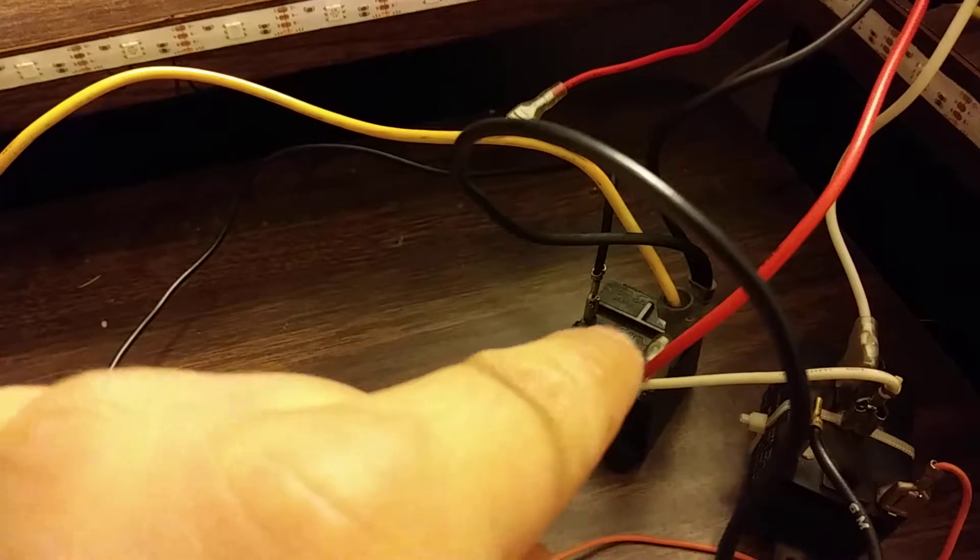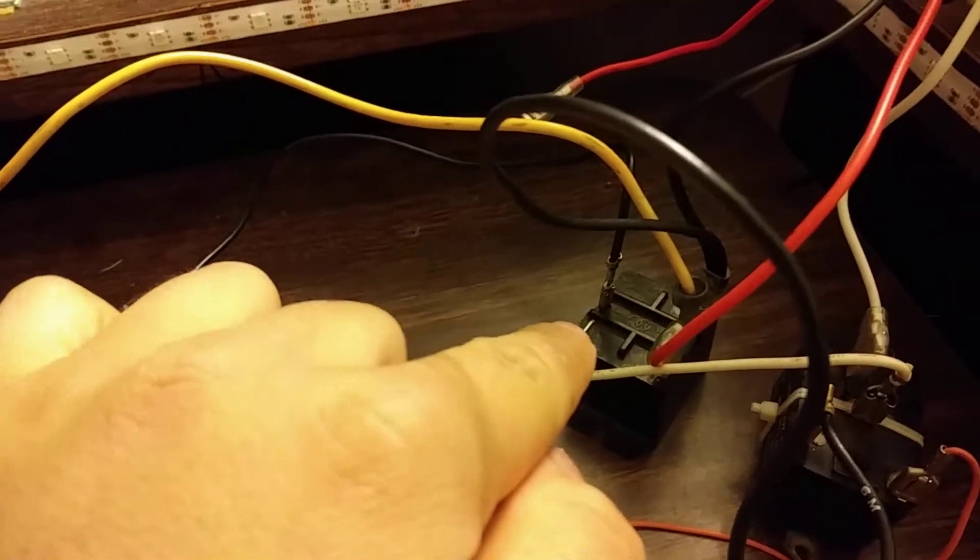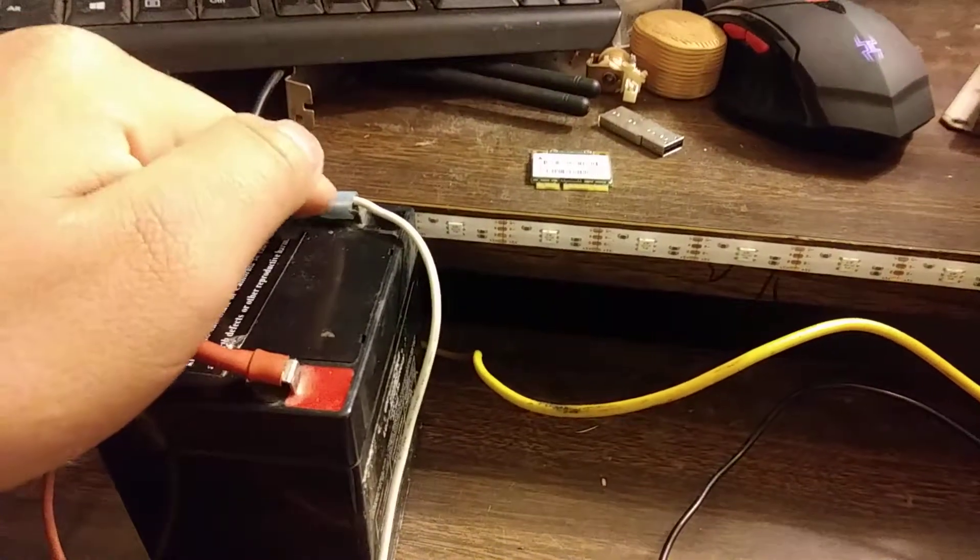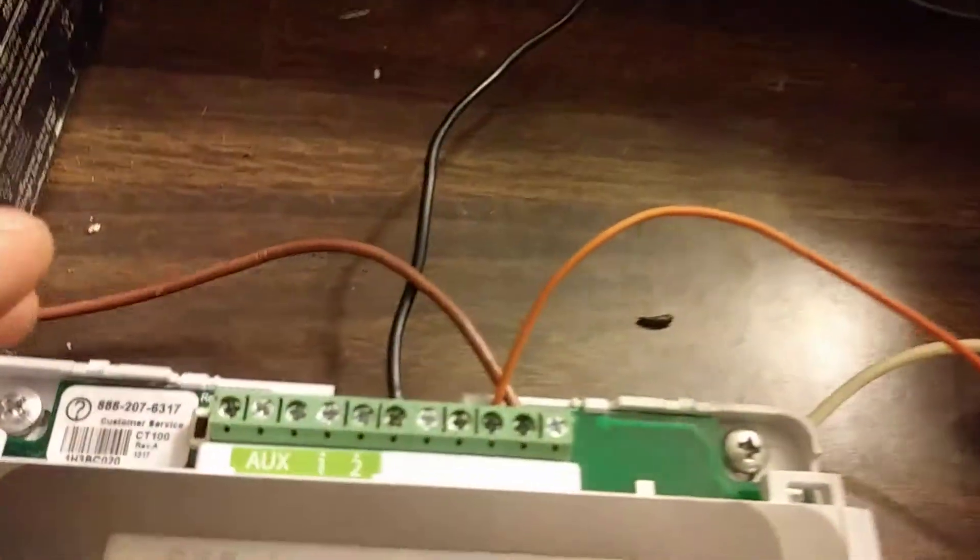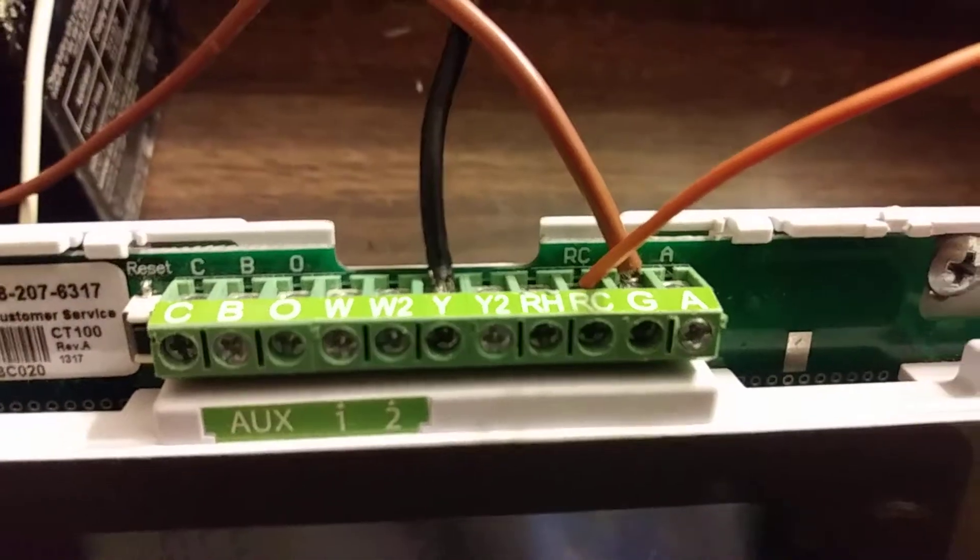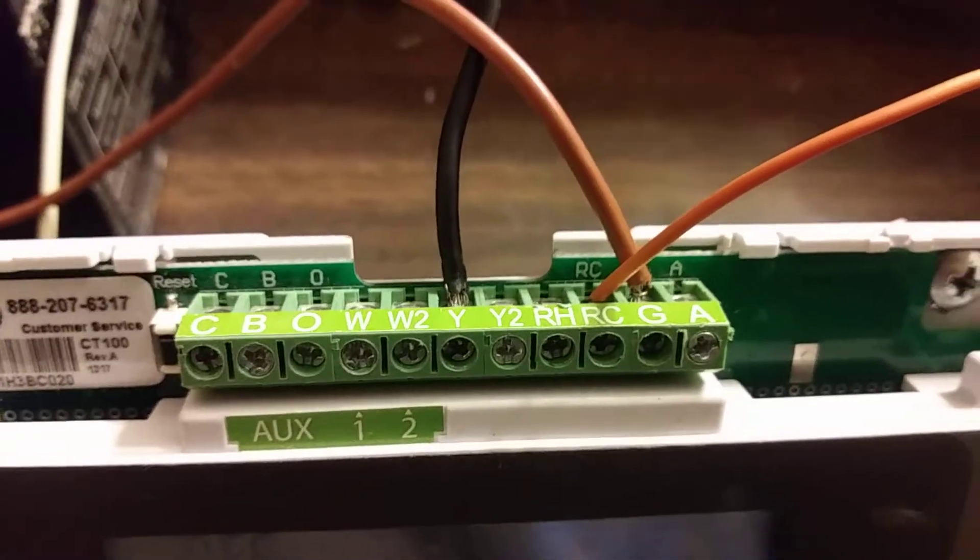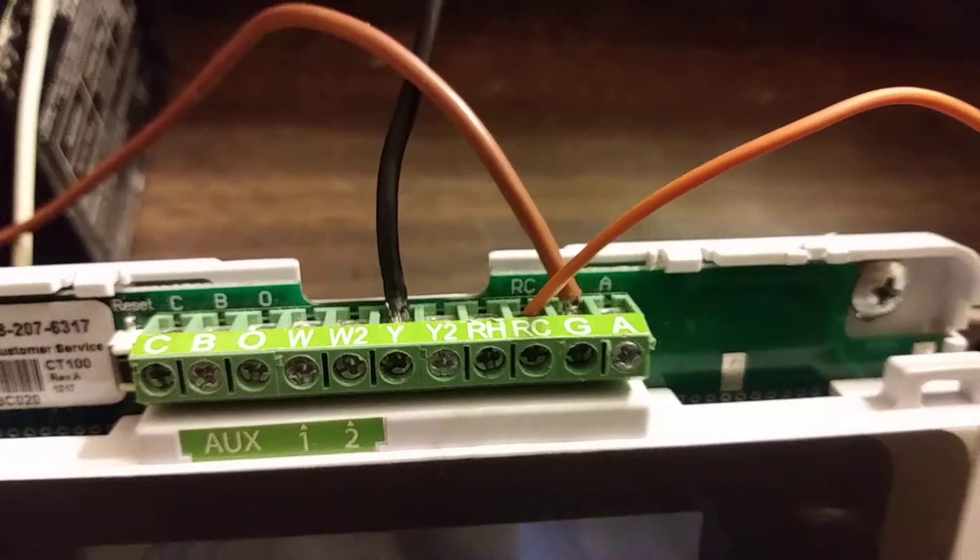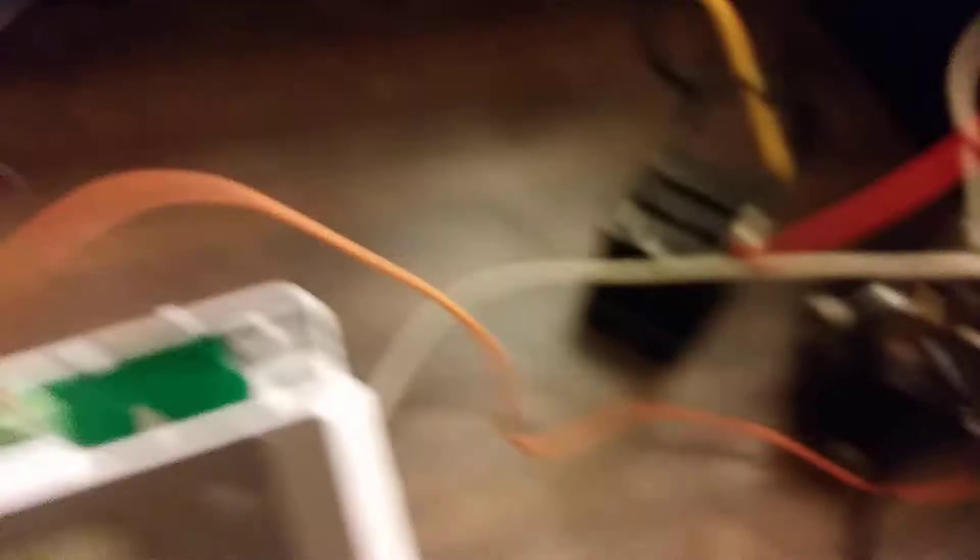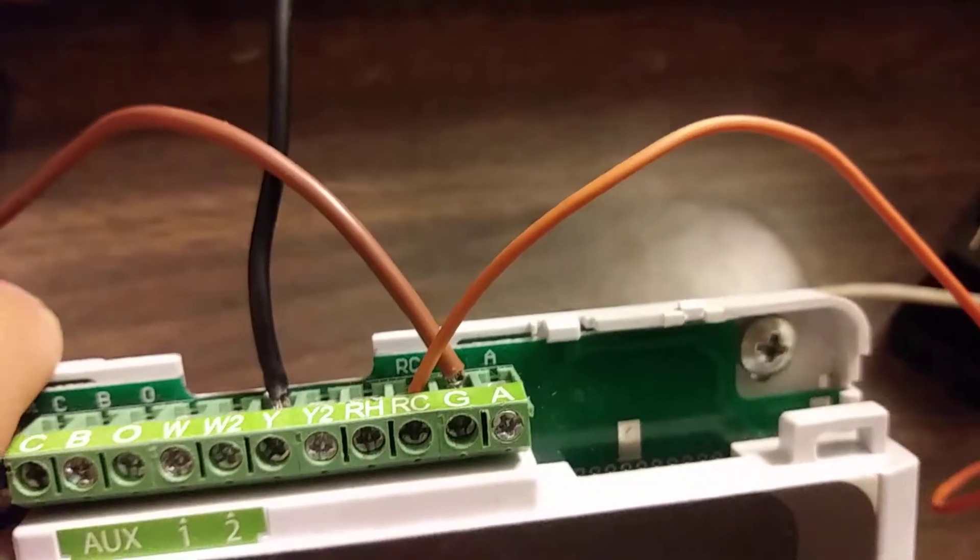And then you're gonna take the other lead to each of them. For example, this black one, this small one, this one right here, the yellow one is connected to my negative side of my battery. And then this other one, the black one, you're gonna connect it to the Y terminal of the thermostat. See the Y right there. You're gonna connect that to the Y. That's gonna be your compressor control or your compressor relay. Then you're going to take the fan relay, the other terminal of that one, you're gonna stick it to RC.